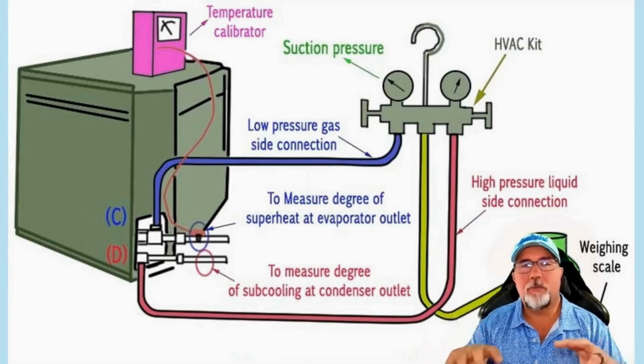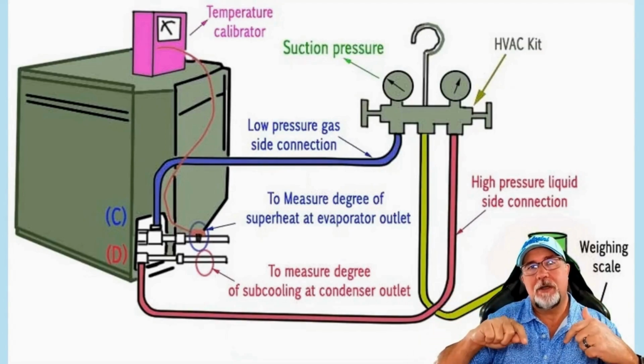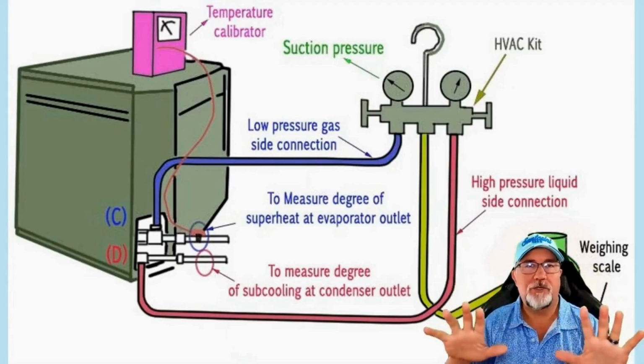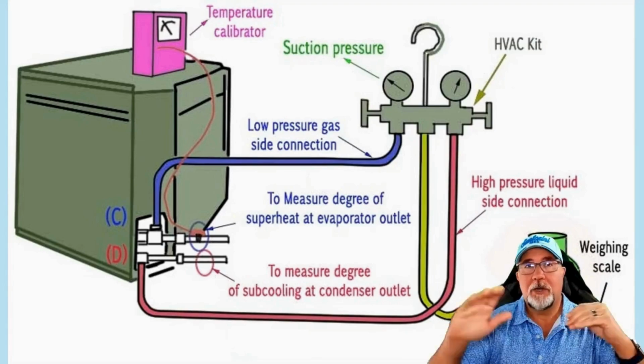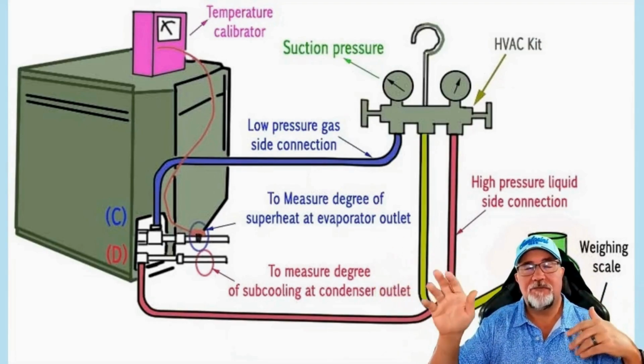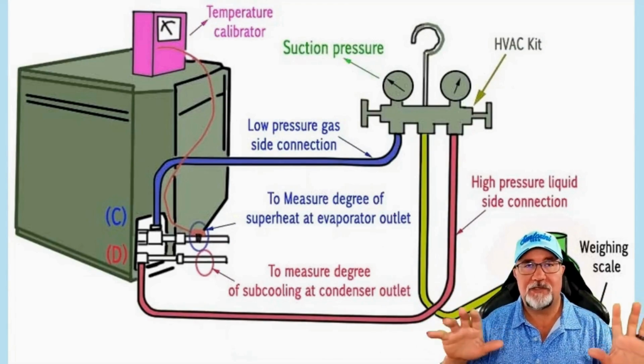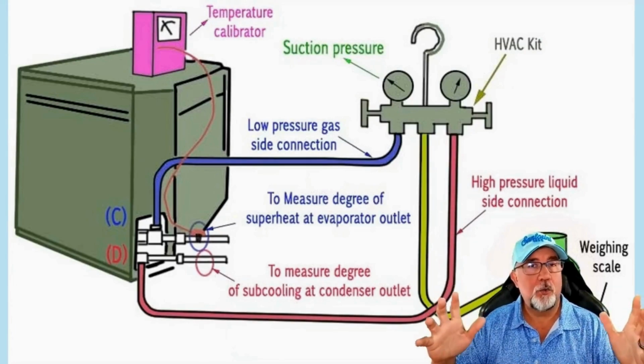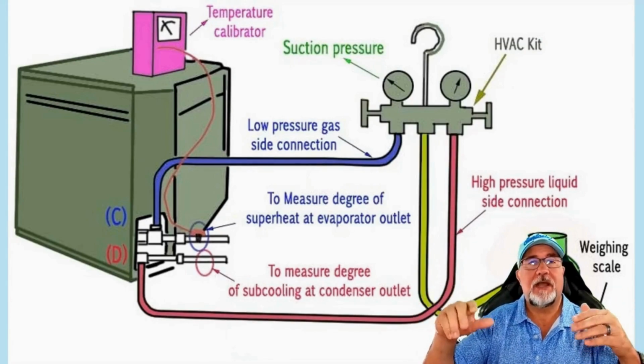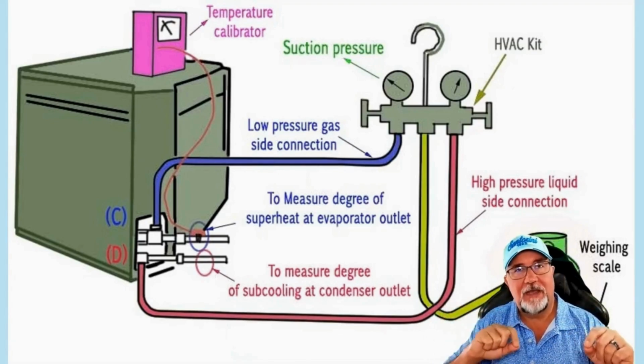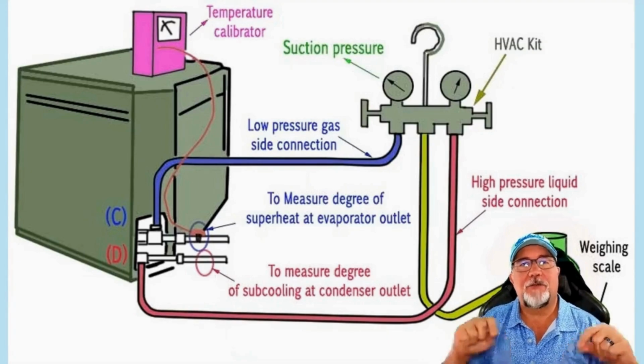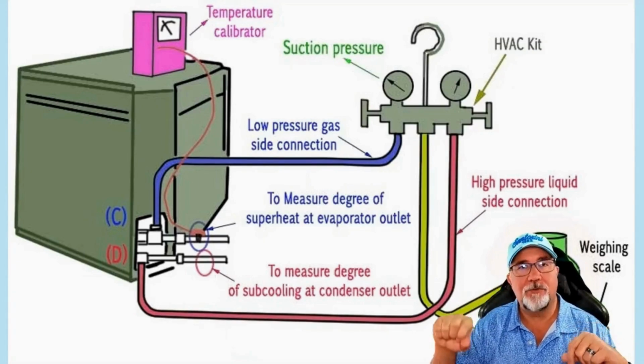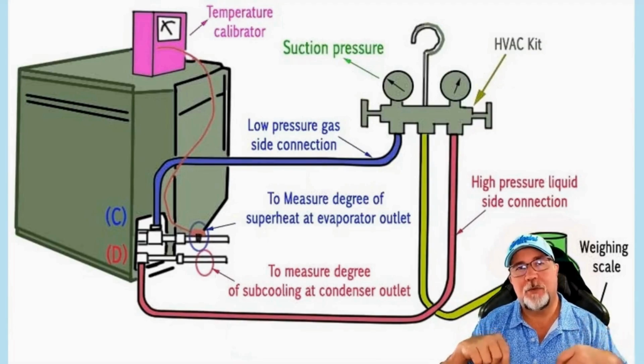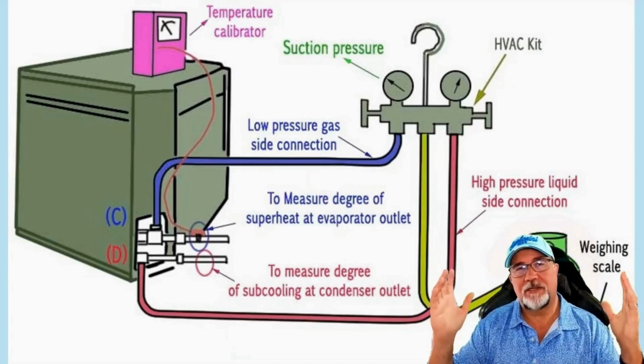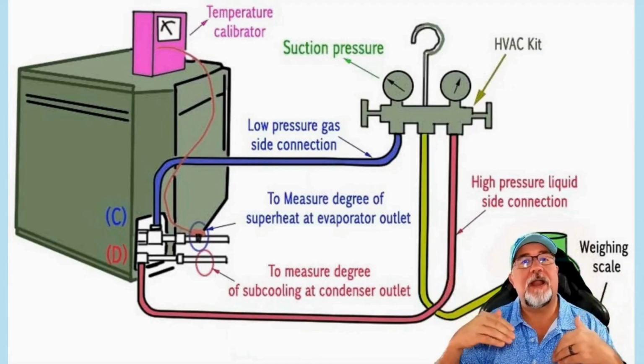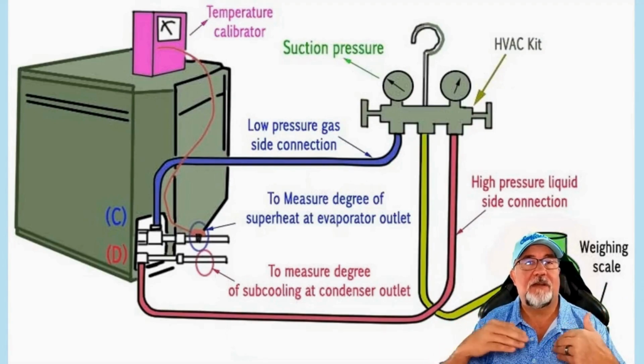Now, when they charge it properly, the manufacturer is going to say 15 feet, but they need to look at the subcool and superheat when they're charging and then know how much refrigerant line length they have. Is it 50 feet, 60 feet? Then, depending on the system, they may be weighing the refrigerant. Some of the newer systems, like Trane, have a system with its own monitoring. But then again, it's like using a calculator. If you use a calculator, you start to forget how to run those numbers in your head and you get complacent. Somebody goes out there, pushes a button, and the light says, oh yep, I'm charged properly, without anybody actually being able to verify that the technology is functioning.